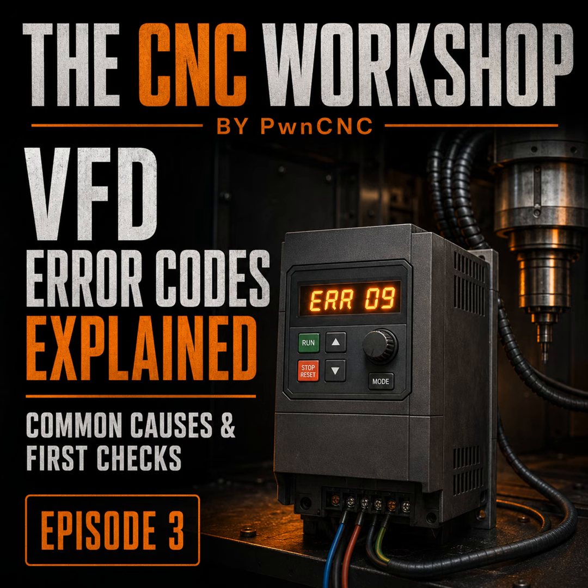This is where the timing of the error becomes really useful, isn't it? Very useful. Suppose the spindle completes its warm-up while the machine is stationary, but ERR12 appears when the gantry begins moving. That strongly suggests inspecting the moving cable system before changing VFD parameters. Because the cable flexes when the machine moves. Exactly. We've seen an installation where the spindle ran normally until machine movement caused ERR12. The power cable was packed into a drag chain with too little room and too tight a bend. Removing the cable from the chain stopped the error. Putting it back caused the error to return. A larger chain and a more generous bend radius resolved it.